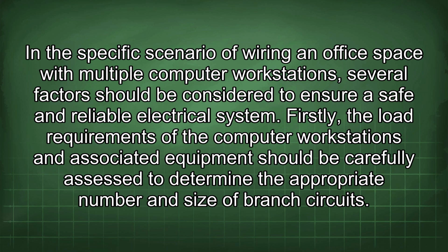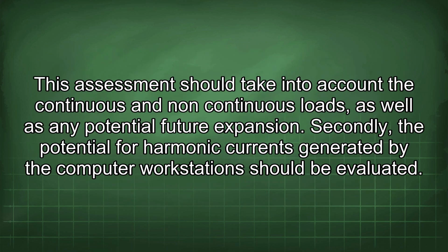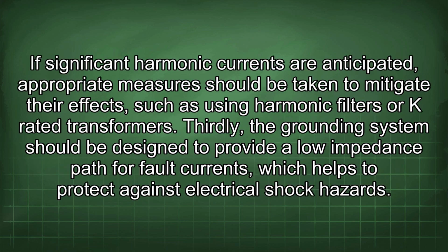Firstly, the load requirements of the computer workstations and associated equipment should be carefully assessed to determine the appropriate number and size of branch circuits. This assessment should take into account the continuous and non-continuous loads, as well as any potential future expansion. Secondly, the potential for harmonic currents generated by the computer workstations should be evaluated.